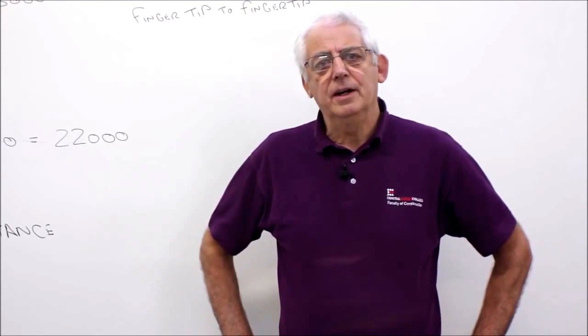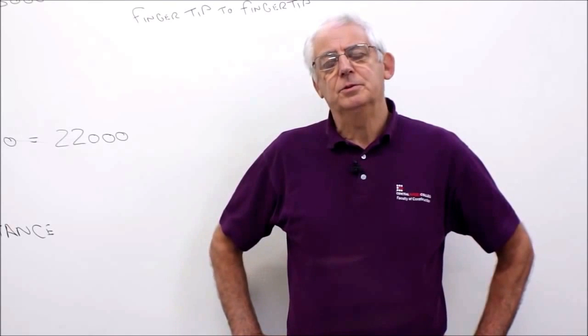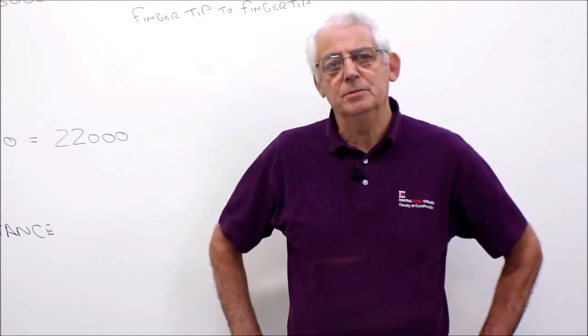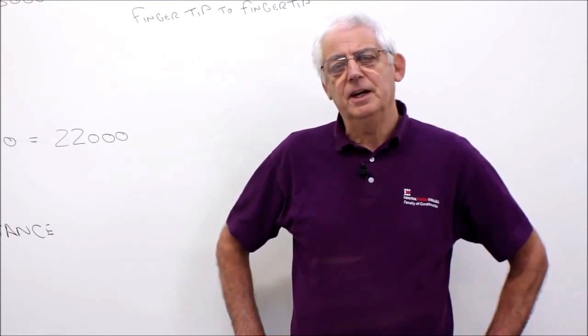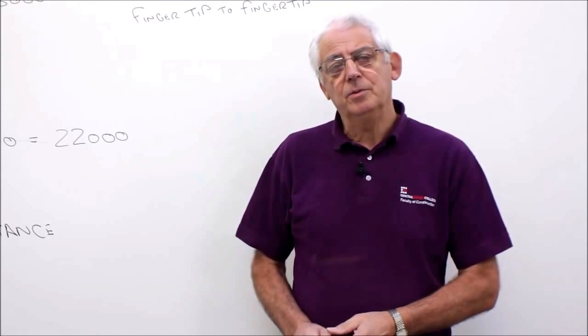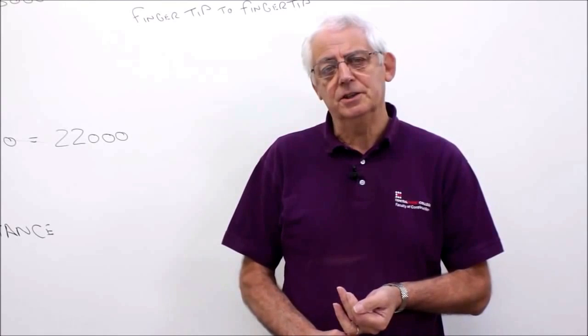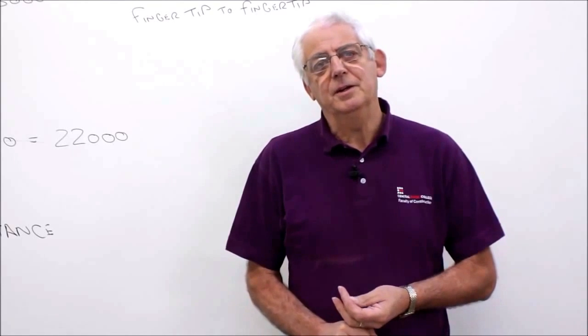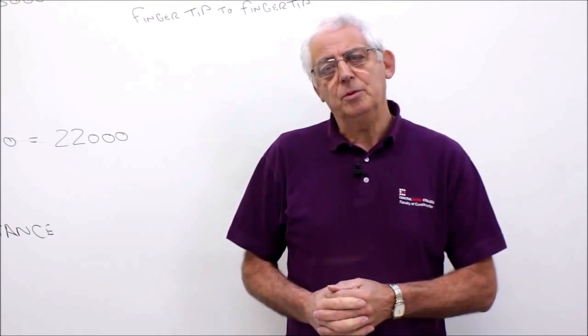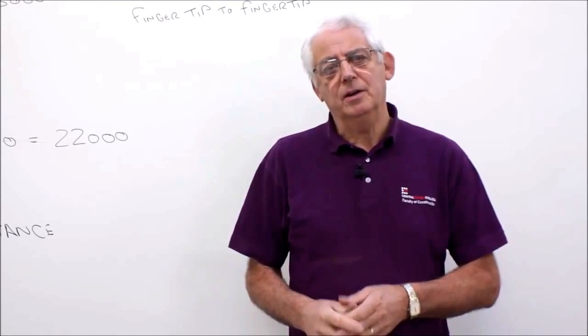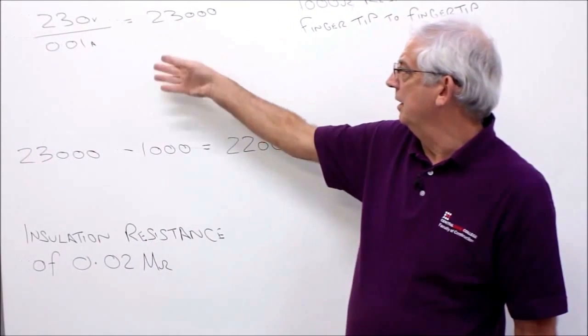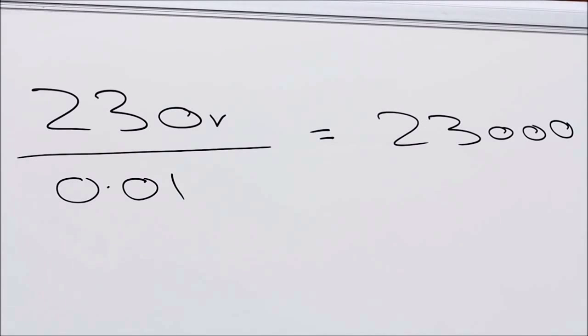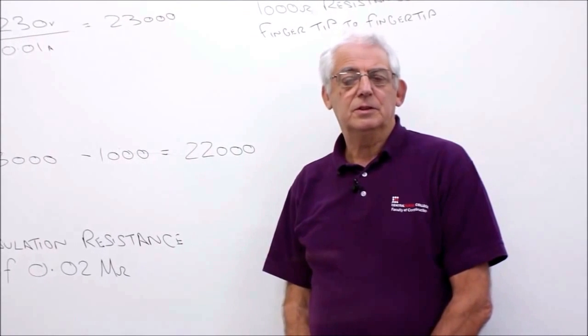The problem we've got when carrying out this type of measurement is that very often our instruments won't measure 1,667 ohms. A lot of them only go up to 99.9. If you're lucky enough to have one that measures kilo ohms, then that's fine. But if not, we have to take another approach. Guidance notes tell us that the maximum shock current that we should really permit in a bathroom, none at all really, but in the event of a fault, would be 10 milliamps. And from that, we can work out our resistances between pieces of equipment to see whether or not they're an extraneous conductive part or whether they're just a piece of metal. So if I divide 230 by 10 milliamps, I'm going to end up with a value of 23,000 ohms. That's pretty difficult to measure with a normal piece of equipment. So at that point, we would have to go to an insulation resistance tester.